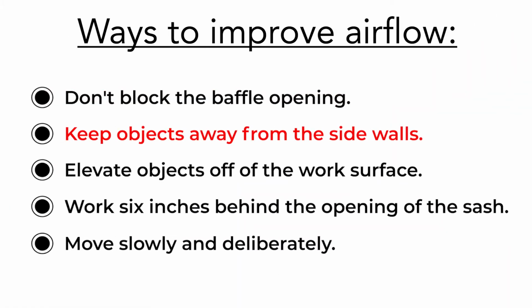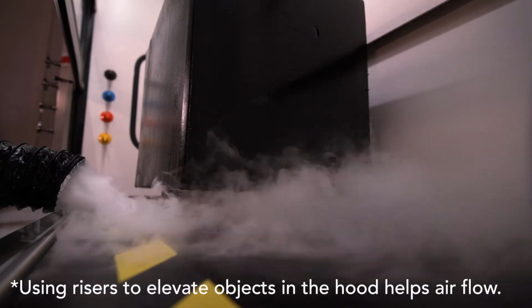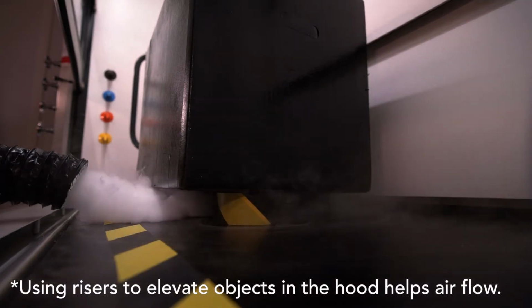As a user, there are things you can do to improve performance. Don't block the baffle openings. Keep objects away from the sidewalls. Elevate objects so they don't sit directly on the worktop. This allows the air to flow under them on its way to the baffles.